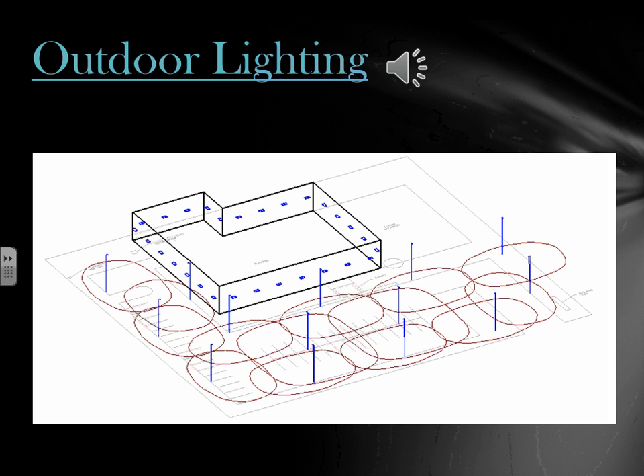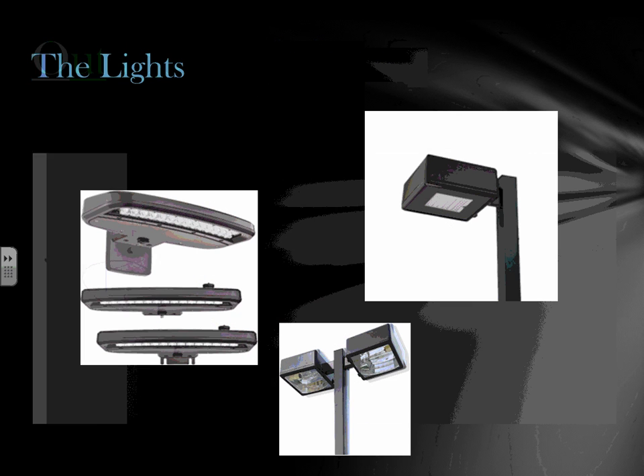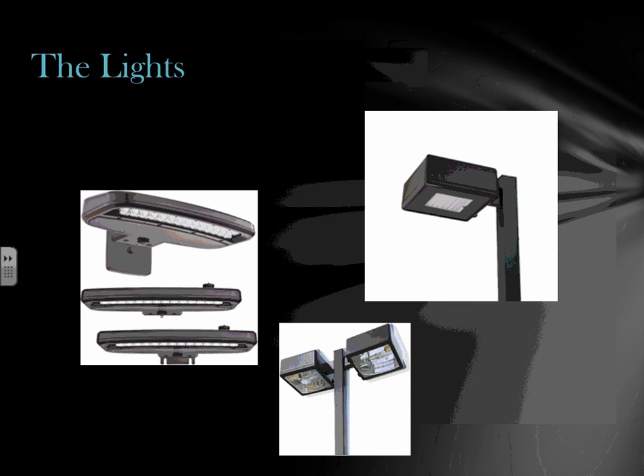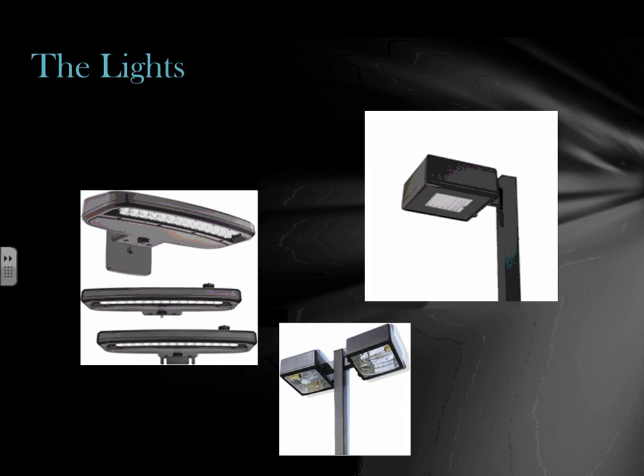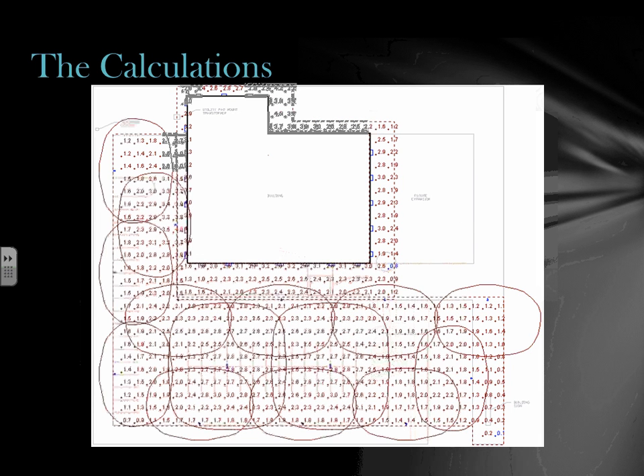Building, so that we have some light in that space. And those are just some visuals we get. We have a couple of double heads and a bunch of single lights around the edges there. And the canopy lights are just mounted on the side at 9 feet. And the street lights are 30 feet up, just so you can get that visual as well. They needed to have a minimum of 1 foot-candle from the outside, and they must have a 4:1 ratio. We're pretty much mostly within about 2 to 3 foot-candles, so we're well within where they're required for us to be. So you can see your car, you can find out where you're going, and you don't have to worry about tripping on that pothole.